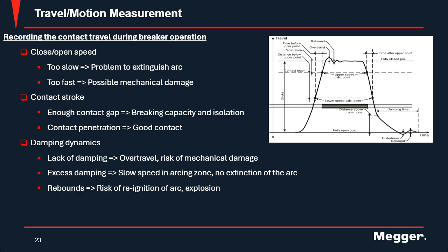So for travel and motion measurements, you can get a lot of information from your travel trace or curve that you're given. Any high voltage breaker is designed to interrupt the short circuit current in a controlled manner. This puts great demand on the mechanical performance of all the components inside your high voltage circuit breaker, components such as the interrupting chamber, as well as the operating mechanism. It has to operate at a specific speed to build up adequate pressure to allow for the cooling medium, such as the air, the SF6, or the oil, to extinguish that arc that is generated after contacts are separated until the next zero crossing.